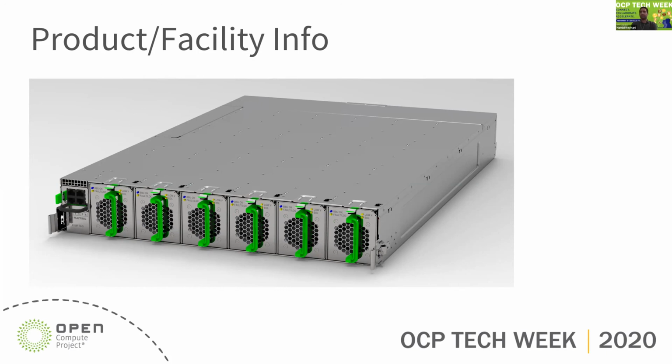All right, one last question. What is the maximum long-term operating temperature for the BBU? Can we use immersion cooling for the BBU? No immersion cooling. The maximum temperature is 45 degrees C, but for long term, it's 35 degrees C.